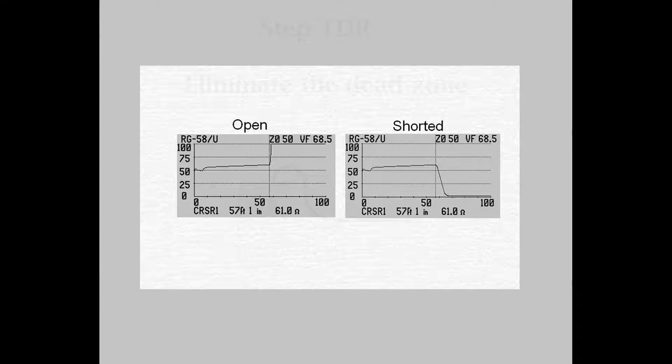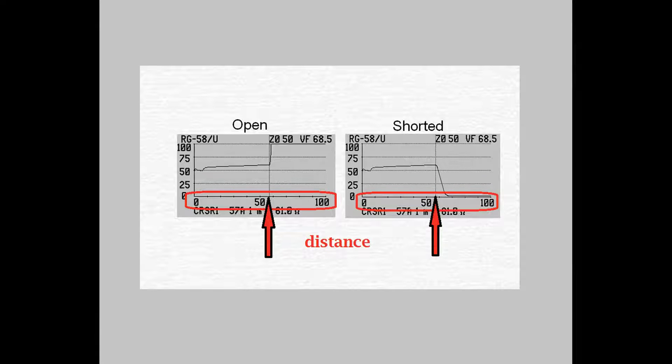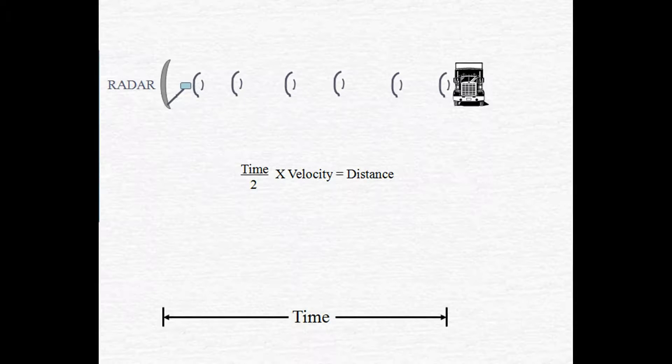So when looking at the TDR screen, the calculated distance of your fault will be displayed at the bottom of the screen. Speaking of distance, let's go back and take another look at how we calculated it. We timed how long it would take a radio wave traveling at the speed of light to make it from our target back to our receiver. Our velocity was the speed of light. Now here's the catch. We've got a little problem. When your electrical impulse is traveling down a wire, it does not travel at the speed of light.